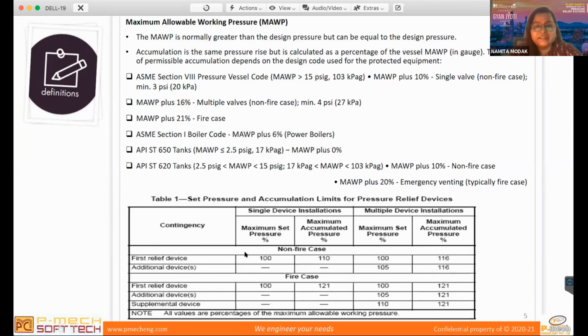So here is the criteria given for the single device installation and multiple device installation. What it says is, if you have 2 orifices, it's normally 2 working, 1 standby. So what will be the set pressure and relieving pressure for the first orifice, and what will be the set pressure and relieving pressure for the second PSV? This table is telling about that also. If you see the first relief device, its maximum set pressure is 100% of your design pressure. So let's take design pressure as 10 bar gauge. Your first relief device is set at 10 bar gauge, and then the maximum accumulated pressure. This is for the non-fire case. For the non-fire case, the maximum accumulated pressure is 10% above your design pressure. So here my set pressure is 10 bar gauge, but my relieving pressure will be 11 bar gauge.